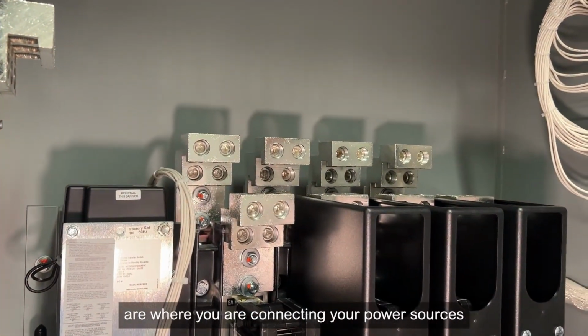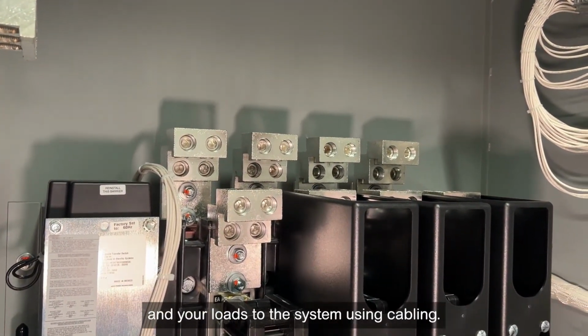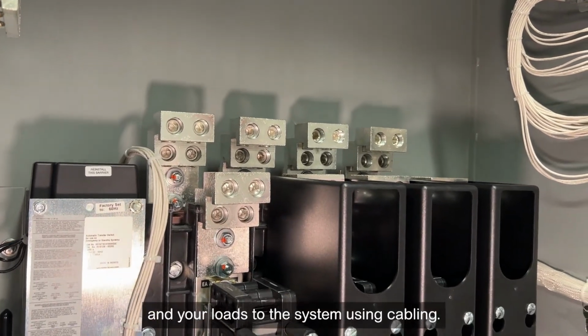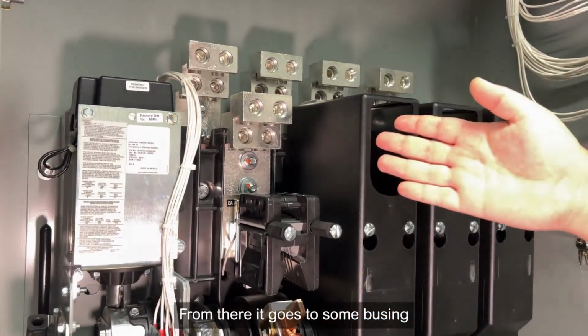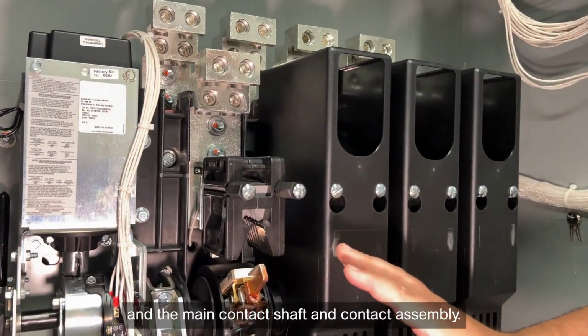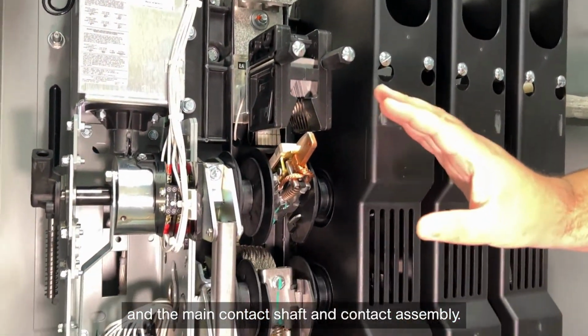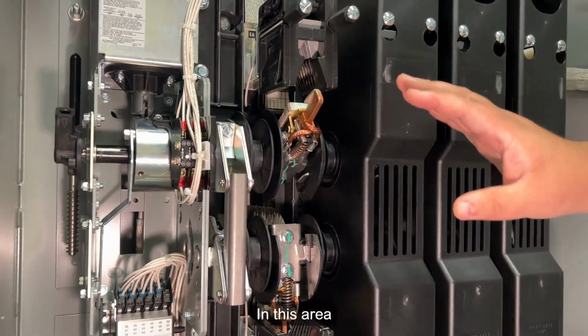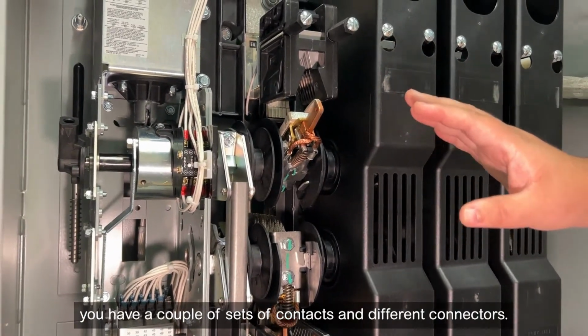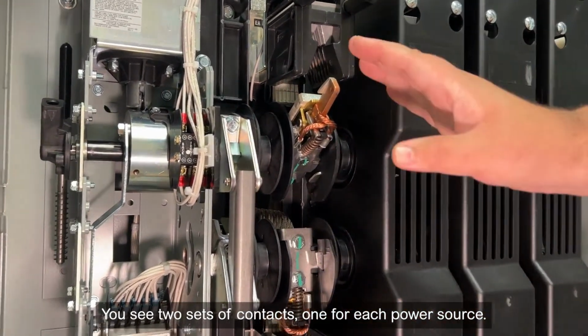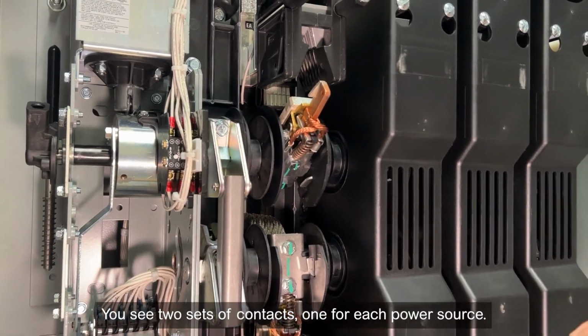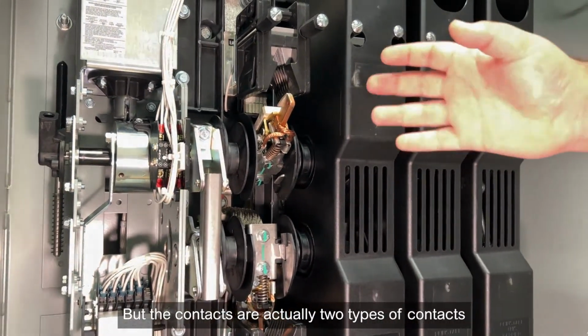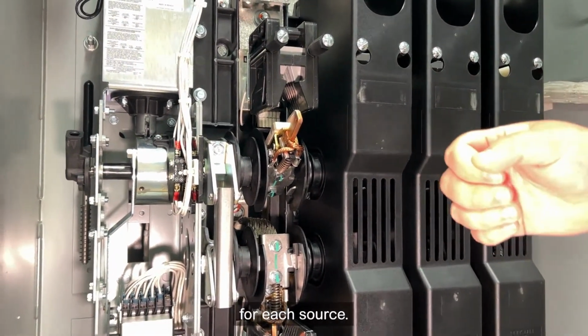The lugs are where you are connecting your power sources and your loads to the system using cabling. From there, it goes to some busing and the main contact and shaft and contact assembly. In this area, you have a couple sets of contacts and different connectors. You see two sets of contacts, one for each power source. But the contacts are actually two types of contacts for each source.